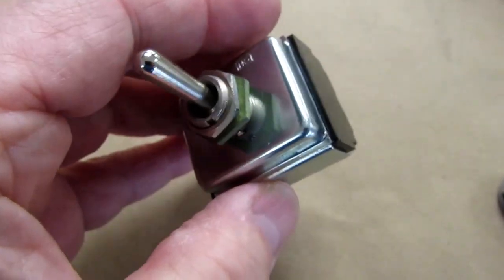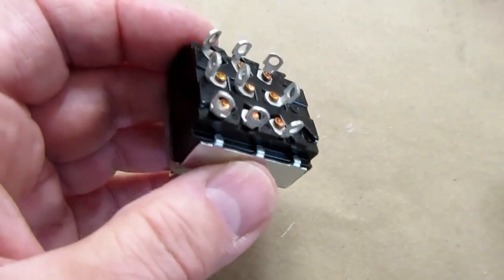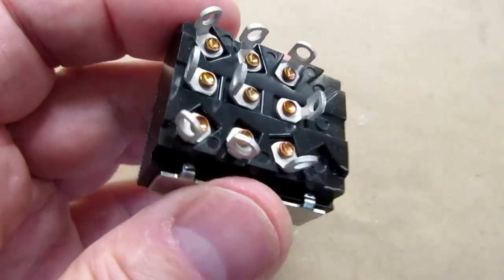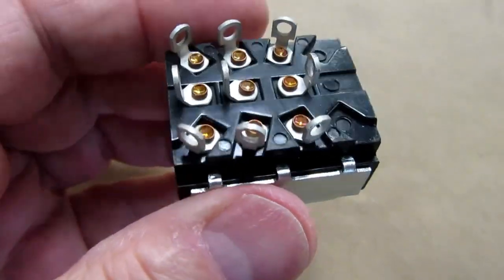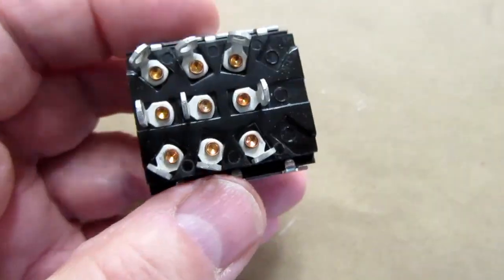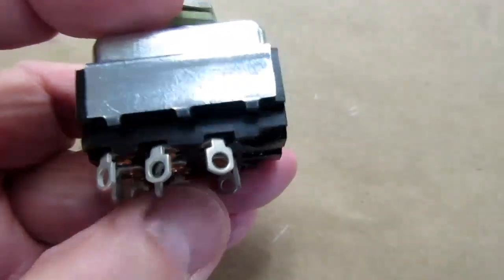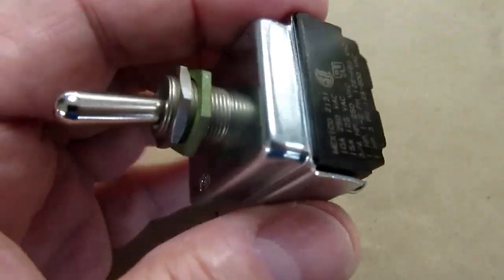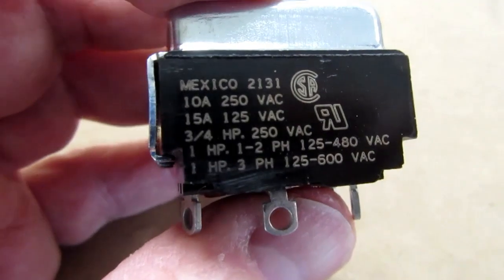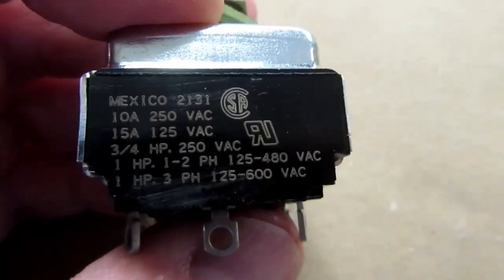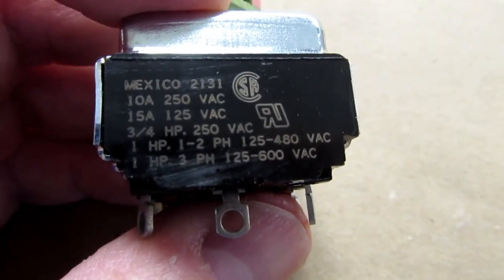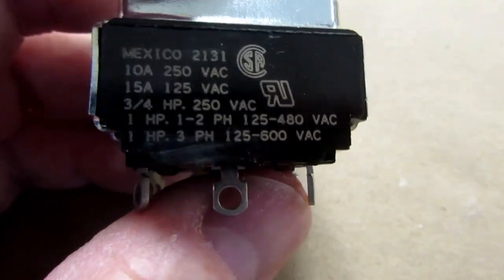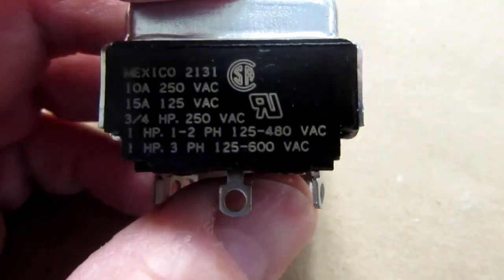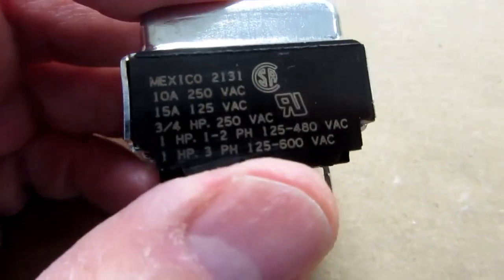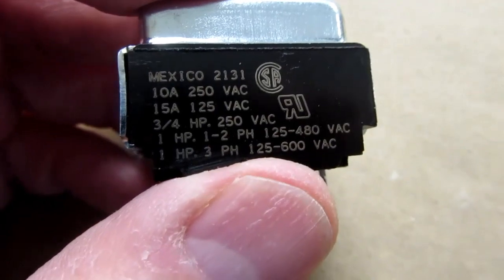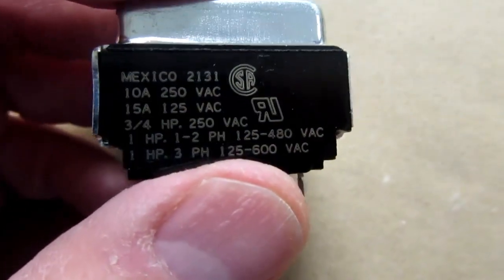Alright, here's a 3PDT 2-position toggle switch that I bought. It's an Eaton/Cutler-Hammer part, so it should be pretty good quality. I bought this from Newark Electronics. It was the only place that had stock on them that did not have a minimum purchase, although I still bought 2 just because I thought it would be handy to have another one like this. It's rated for motor use, so it's really intended to be used in motor circuits, and the spec sheets are all about its AC ratings. I contacted Eaton Tech Support for this particular product line, and they just said there are no ratings on this for DC use, so you're going to have to interpolate, but we can't make a recommendation because we're not allowed to read between the lines.